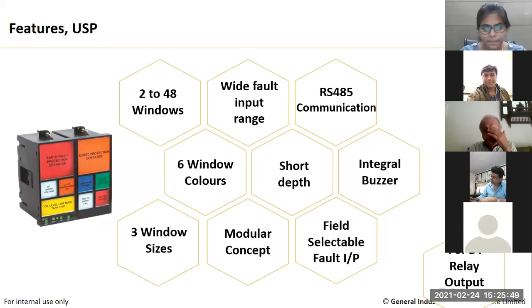Our next feature is field selectable fault input, so we can select the fault input on the field, whether it is NO or NC. The next is 4 SPDT relay output, also an important feature. We have 4 relays in a device: 2 relays for grouping, group 1 and group 2; the third relay is for hooter, which we can connect externally even though we have an internal buzzer; and the fourth is for ring back or supervisory feature.